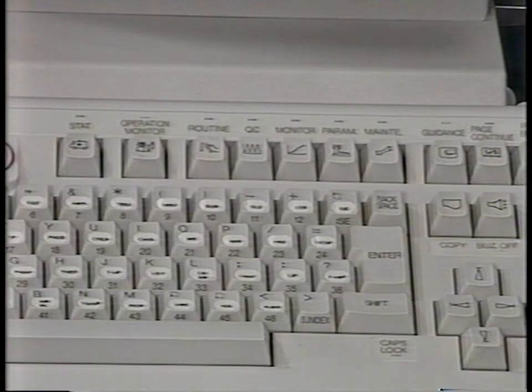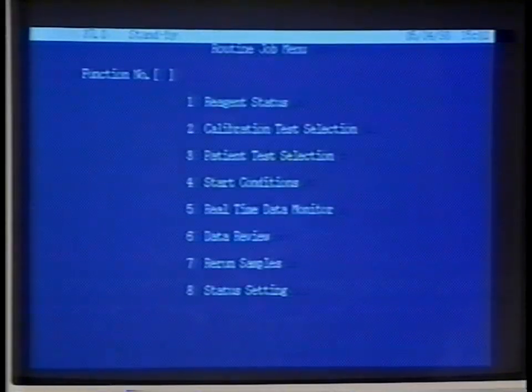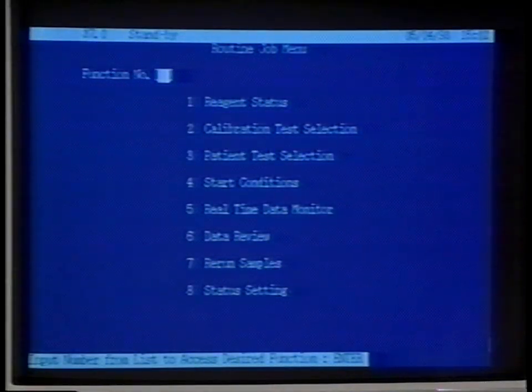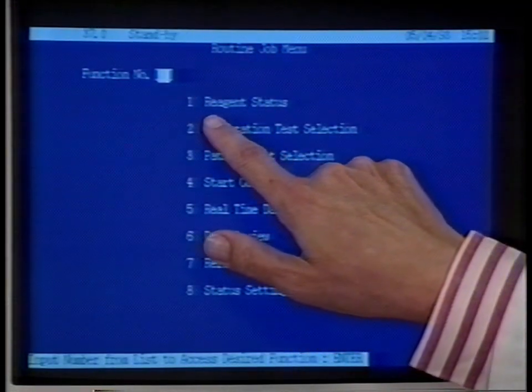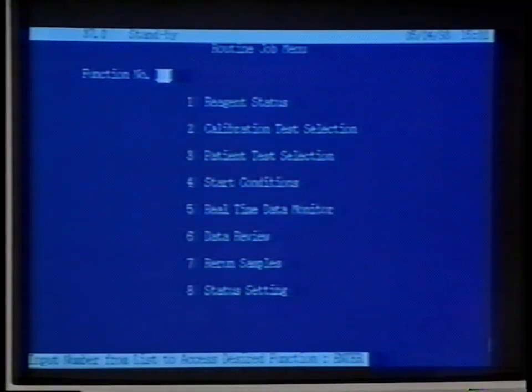Pressing the routine job key accesses its menu as we saw before. The screens in this job group allow you to view the number of tests remaining for each reagent, request calibrator selections, and select tests for routine patient samples. The Start Conditions screen can be utilized as a checklist prior to initiating operation and sample processing. The Real-Time Data Monitor screen lets you view partially completed reports.